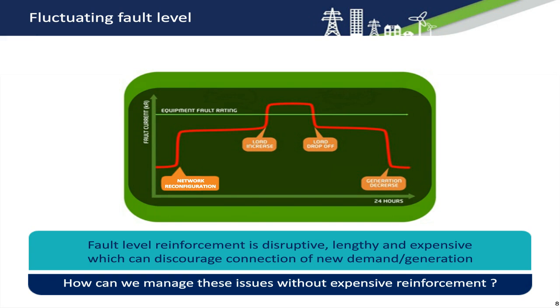When the potential fault current is larger than the rating of equipment, our approach has been to replace the equipment with a higher rated equivalent. This reinforcement is expensive, time consuming and disruptive to customers. And this approach doesn't provide an accurate way of measuring fault level either. The question is, how can we work smarter, predict fault current more accurately and avoid resorting to expensive reinforcement?